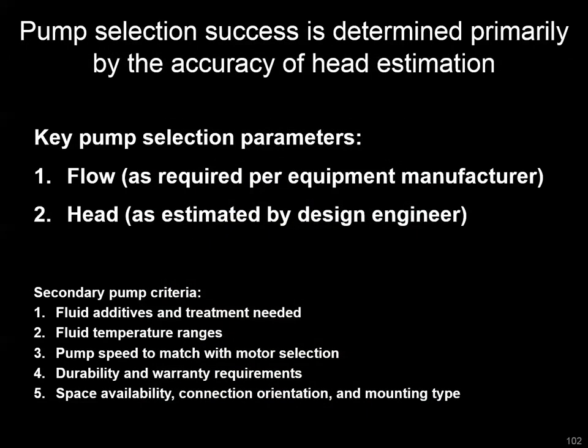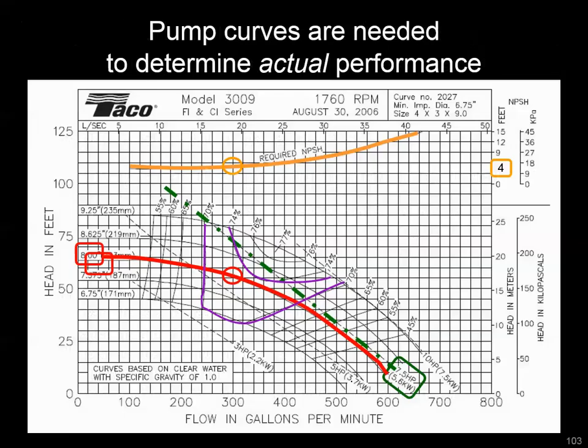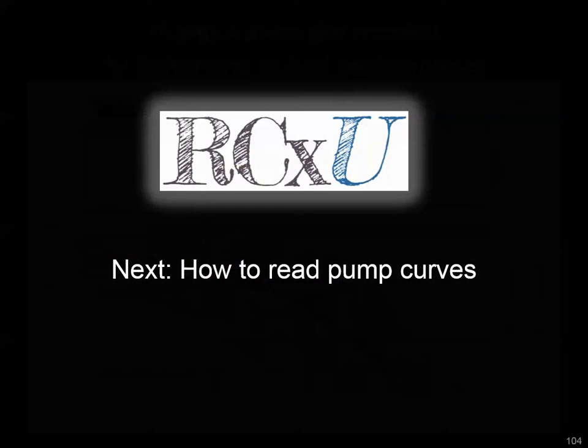To summarize: flow and head are the two key operating parameters. Flow is indicated by design and by the heat exchangers required in your system, and head is estimated by the design engineer. One key point is that it's the actual head your system operates at that's going to determine the flow and the performance of your pump — and we'll see that on the next video with the pump curve.